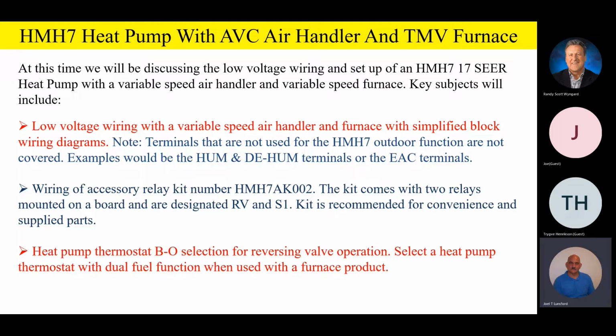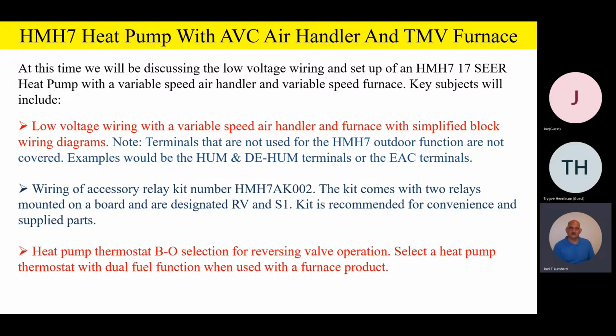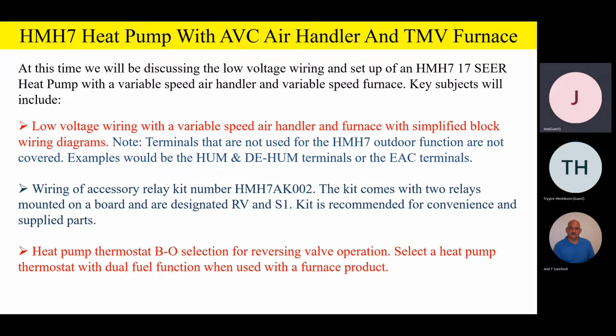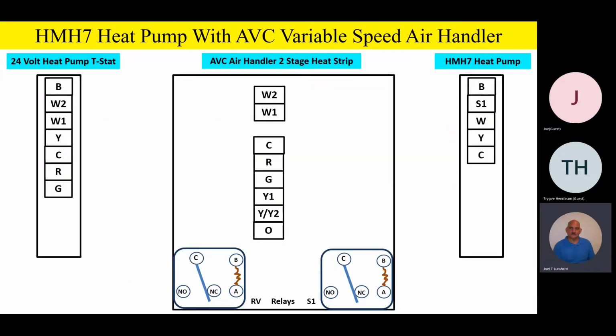However, we provide and we recommend the HMH7AK 002 kit, if it's going on a variable speed air handler or a variable speed furnace. Now, guys, please remember also the heat pump thermostat has to still have that BO selection on this variable speed product, a BO selection for reversing valve operation. And remember to please select a heat pump thermostat with dual fuel function whenever you use the HMH7 in a dual fuel capacity with a heat pump, or more specifically, a furnace product. So with that said, let's go ahead and walk through.